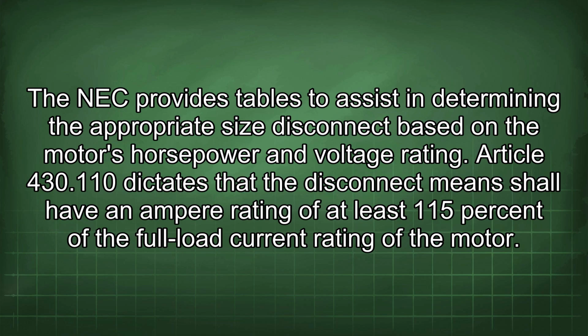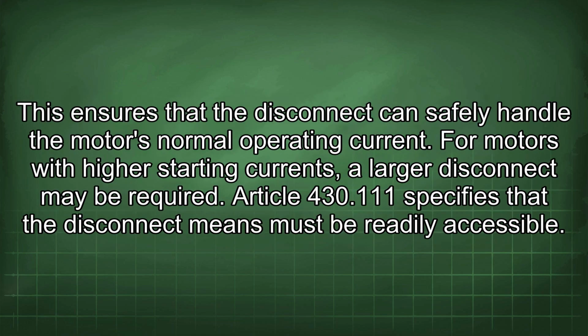Article 430.110 dictates that the disconnect means shall have an ampere rating of at least 115% of the full load current rating of the motor. This ensures that the disconnect can safely handle the motor's normal operating current. For motors with higher starting currents, a larger disconnect may be required.